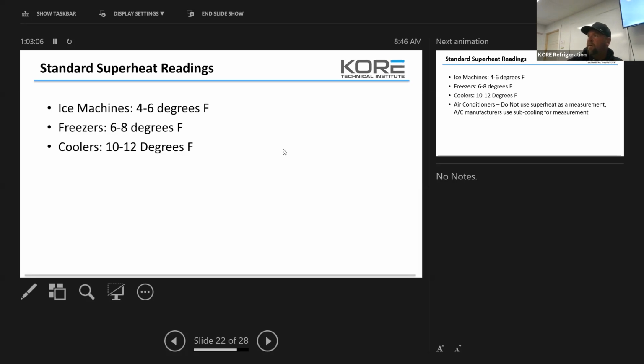So what I would tell you is, these are good rules of thumb to get you in the range, but like we saw with those low profile coils in the Mavericks, we need to run them down more like a freezer. The thing is, when you turn it down that low, where's the next place you're going to check your superheat? At the compressor. That's going to tell you if you're coming back too hard. On any single systems, I don't want to see that lower than 20.